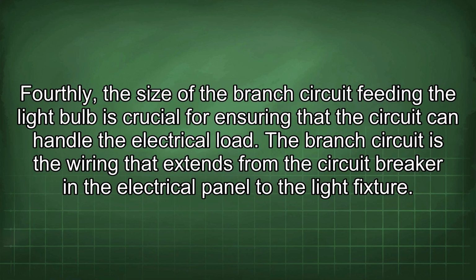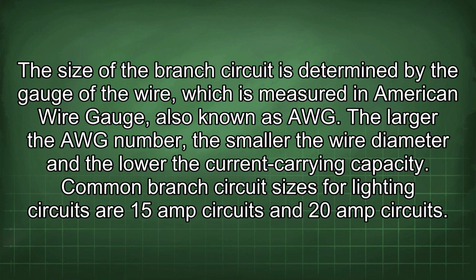Fourthly, the size of the branch circuit feeding the light bulb is crucial for ensuring that the circuit can handle the electrical load. The branch circuit is the wiring that extends from the circuit breaker in the electrical panel to the light fixture. The size of the branch circuit is determined by the gauge of the wire, which is measured in American wire gauge, also known as AWG. The larger the AWG number, the smaller the wire diameter, and the lower the current carrying capacity.